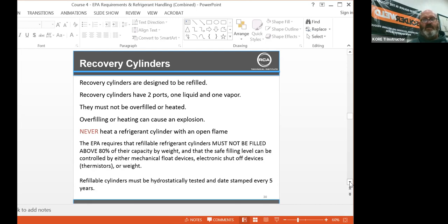Of course, if you are doing a bottle exchange, they're going to take care of that for you. Back in the day there was a recovery system called an OZ Saver, and they actually had to use their tanks. It had a weight on the inside with a cable, and it would fill up to the point and actually cut off the recovery unit.